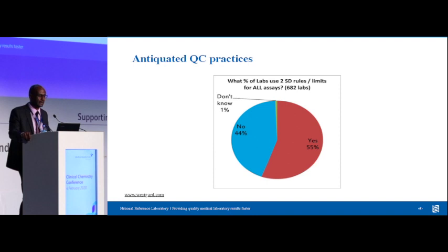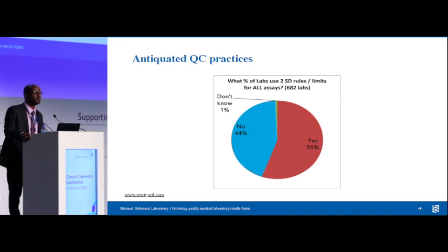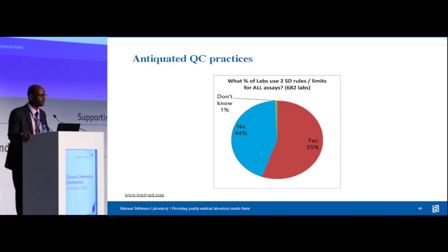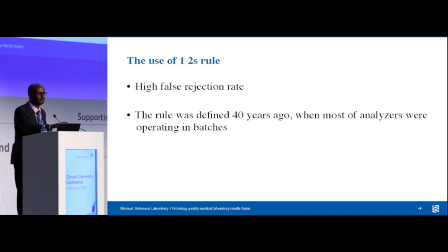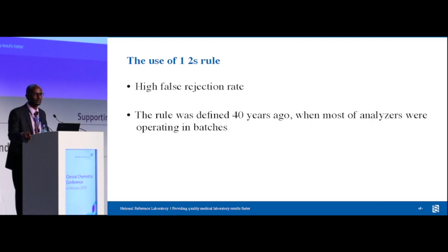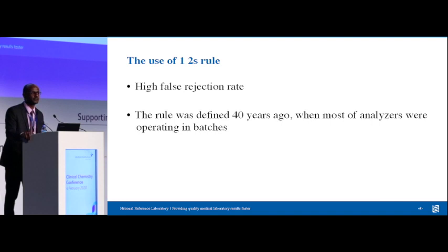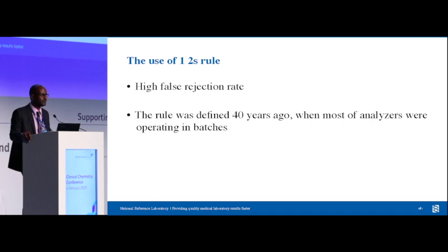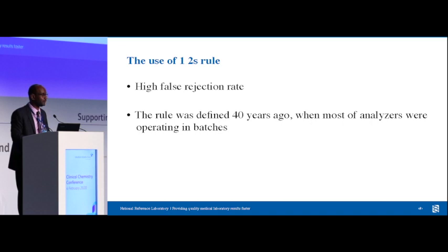Westgard did a survey distributed to global laboratories to see their QC practices. He asked what percentage of labs still use the 2SD rule. Unfortunately, up to 55% of laboratories are still using this outdated 1-2S rule — despite the fact that Westgard himself encouraged laboratorians to stop using it. It was defined 40 years ago when technology was different. Nowadays there are a lot of alerts to tell us when the system is out of control, so there's no need to use this rule because of its high false rejection rate.